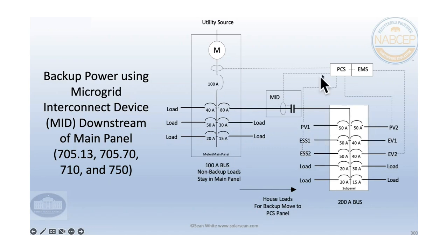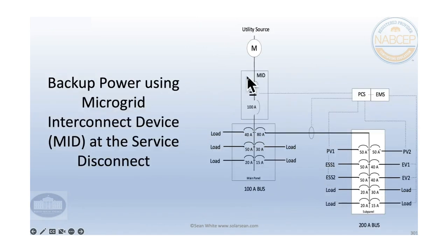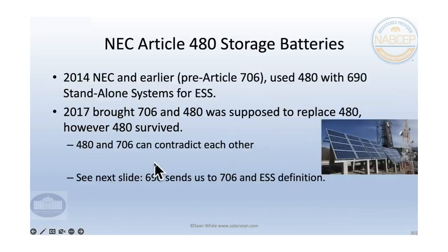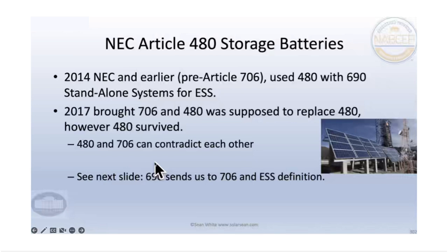And we can control all these currents because they're connected to this energy management system, or you can call it a power control system in 2020 NEC. And so it's all connected with these different CTs. Those are current transformers in different places. So that's 705.13. And then here we are doing it, microgrid interconnect device with whole house backup. And there's the power control system and energy management system. So those things are kind of neat. I like that. So there we go.